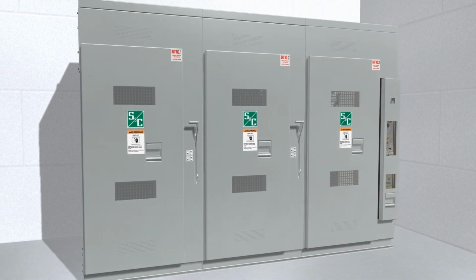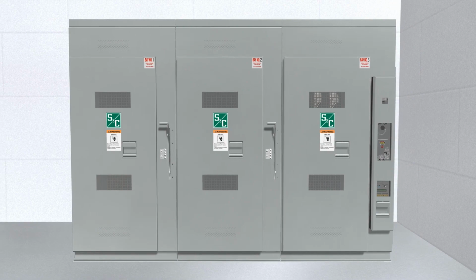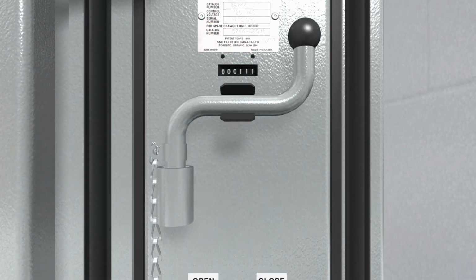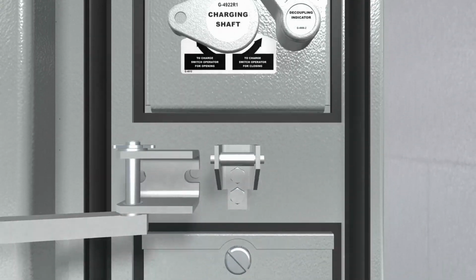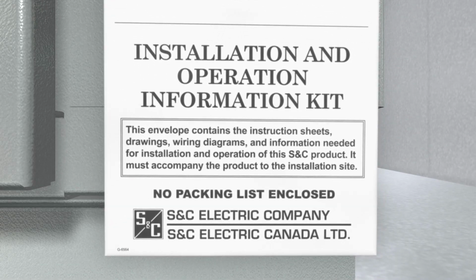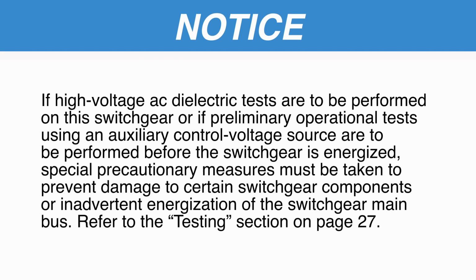If the switchgear is power operated, the switch operators and automatic control equipment may now be checked. Separate instruction sheets for the switch operators and for the source transfer control are included in the Installation and Operation Information Kit provided with the switchgear. Note: if high-voltage AC dielectric tests are to be performed on this switchgear, or if preliminary operational tests using an auxiliary control voltage source are to be performed before the switchgear is energized, special precautionary measures must be taken to prevent damage to certain switchgear components or inadvertent energization of the switchgear main bus. Refer to the Testing section on page 27 of the written instructions.